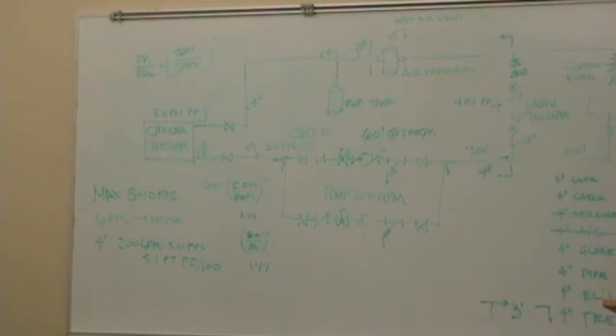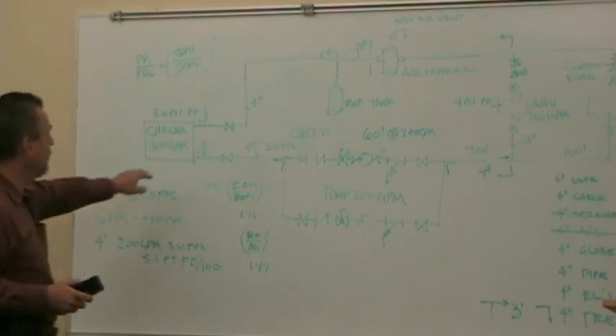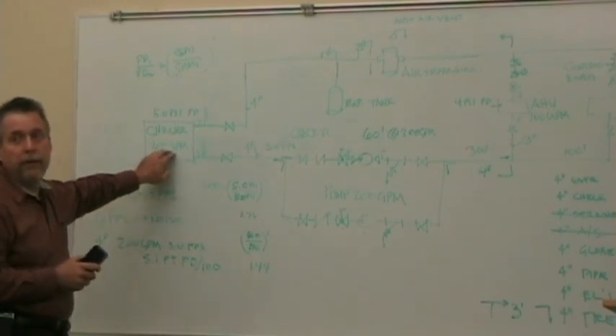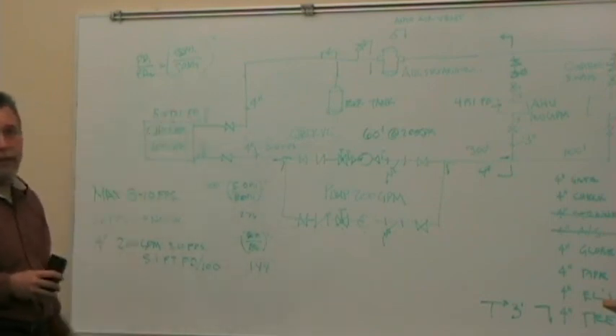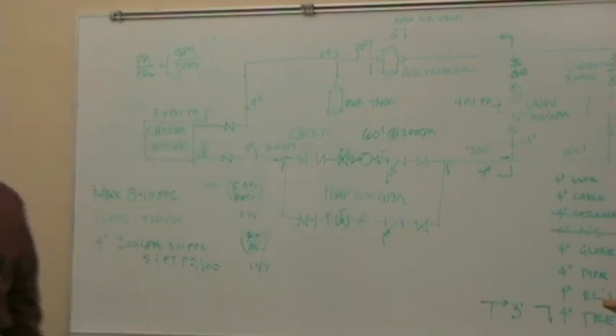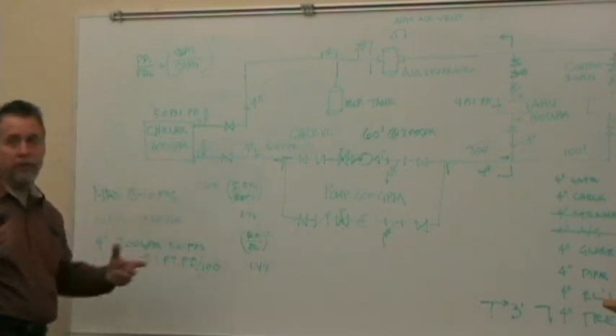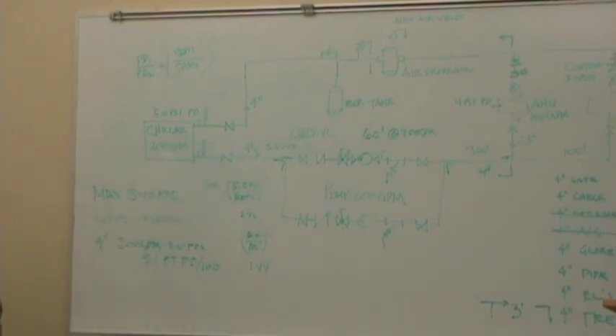And a boiler system would operate just the same. I mean, the boiler might have very low pressure drop here, but pipe calculations and that type of thing are the same. So since boilers have very low pressure drop, if the chilled water system normally operates at 60 to 100 feet, then you'll find boiler systems operating at 40 to 80 feet.